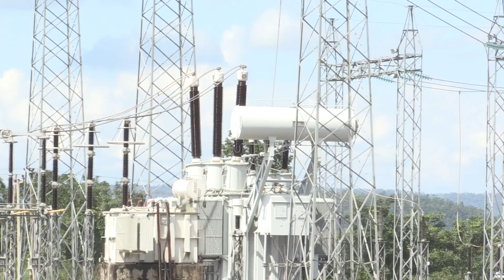What are the key projects executed recently in this region? In this region, the key project executed recently is the installation and commissioning of two 150 MVA transformers, 330 by 132 kV, at our Birnin Kebbi 330 by 132 kV substation. We also installed and commissioned a 100 MVA 132 by 33 kV transformer at our Birnin Kebbi 132 by 33 kV substation. Those are the major projects commissioned recently.